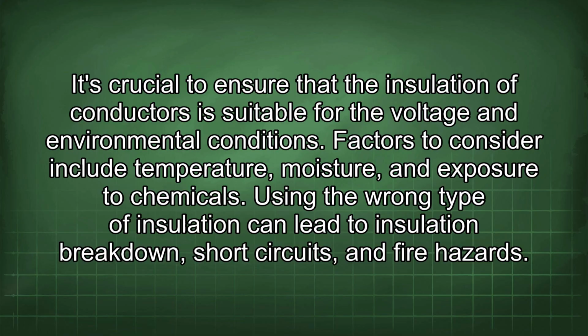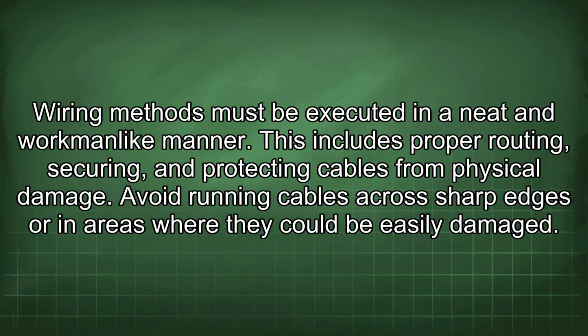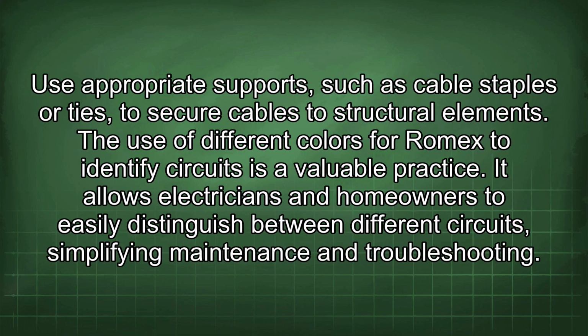It's crucial to ensure that the insulation of conductors is suitable for the voltage and environmental conditions. Factors to consider include temperature, moisture, and exposure to chemicals. Using the wrong type of insulation can lead to insulation breakdown, short circuits, and fire hazards. Wiring methods must be executed in a neat and workmanlike manner. This includes proper routing, securing, and protecting cables from physical damage. Avoid running cables across sharp edges or in areas where they could be easily damaged. Use appropriate supports, such as cable staples or ties, to secure cables to structural elements.